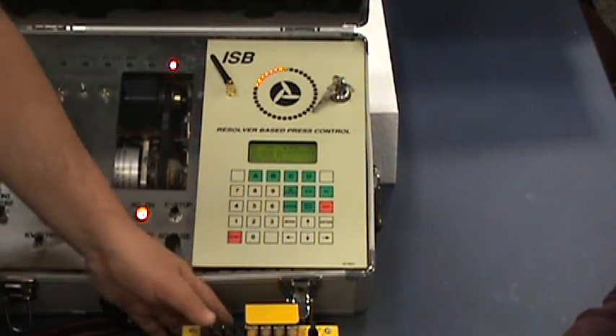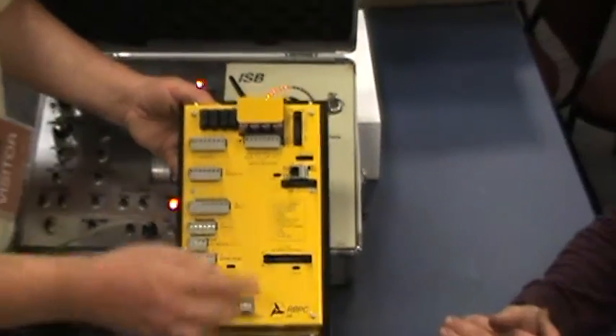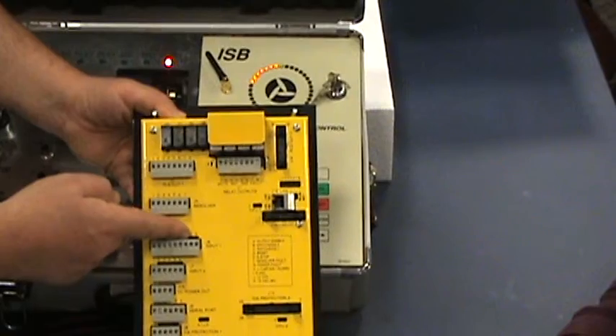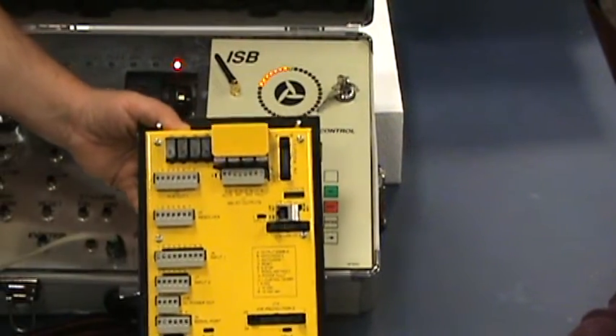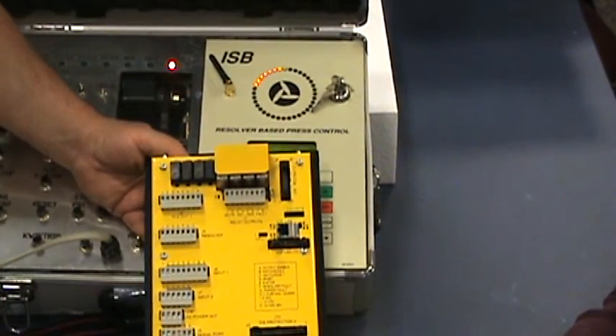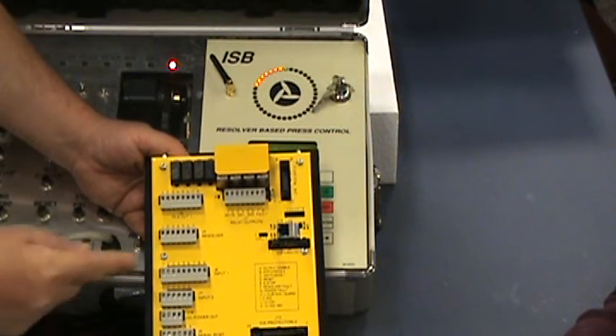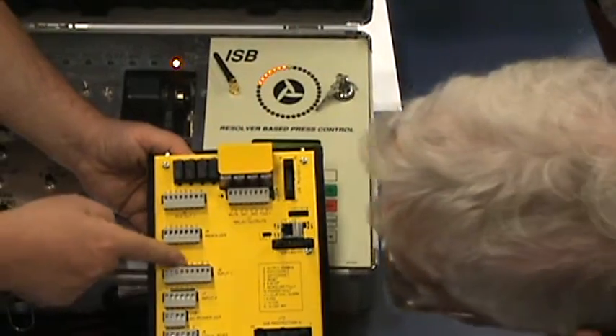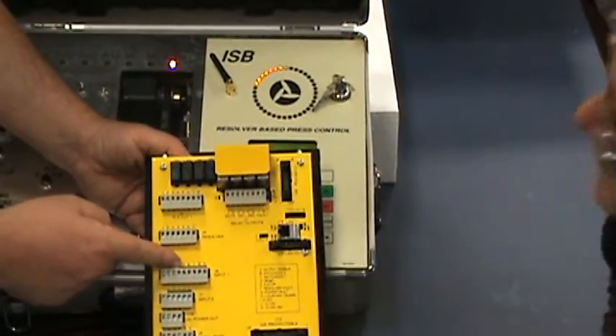And I want you to be aware, at the back side of every Phoenix block that's an input, there is a red LED there. For example, if you're pushing palm buttons and they're not stroking the machine, the first thing to look is in this cutout, have somebody push the push button and it will light up red.